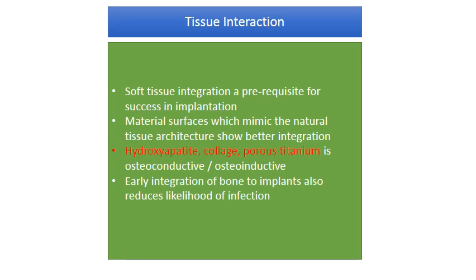The other type are tissue interaction coatings. The idea is that if you want tissue to integrate into the implant — which is a prerequisite for success — then the implant should mimic the natural tissue as much as possible. A number of coatings such as hydroxyapatite, which is a mineral found in bone, collagen, and porous titanium are known to induce and conduct bone formation in prosthetic implants, making them osteoinductive and osteoconductive.